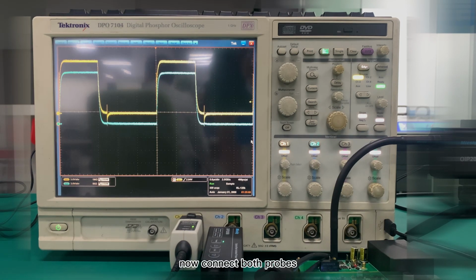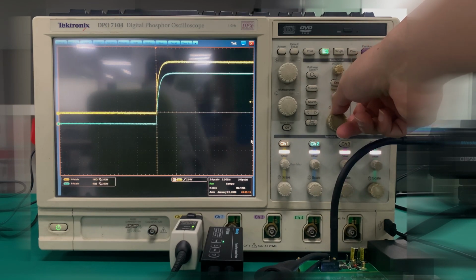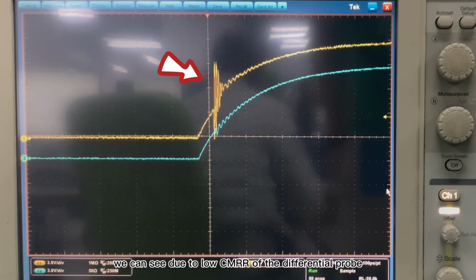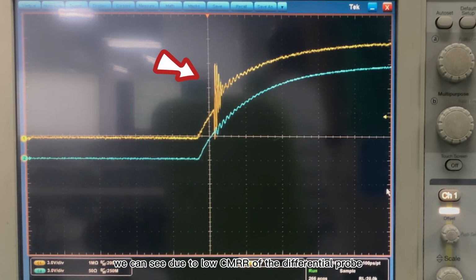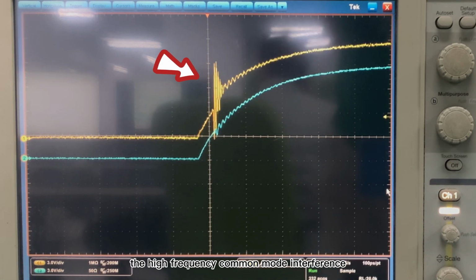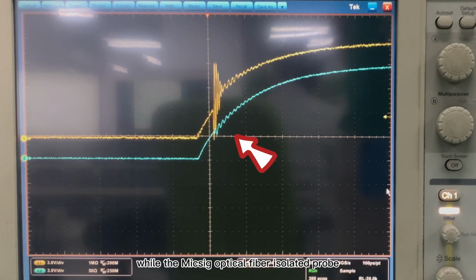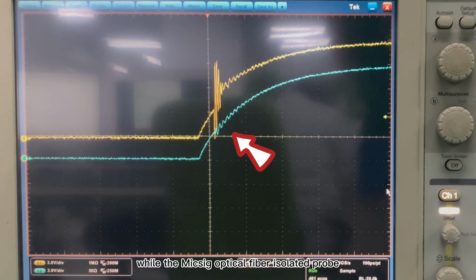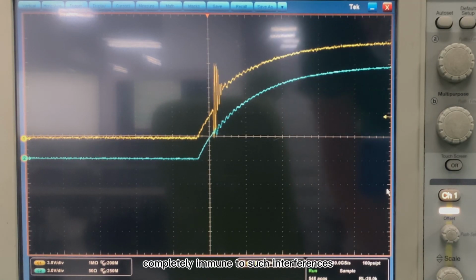Now connect both probes to the high side of VGS at the same time. We can see that due to the low CMRR of the differential probe, the high-frequency common mode interference is not rejected, while the Micsig optical fiber isolated probe is completely immune to such interference.